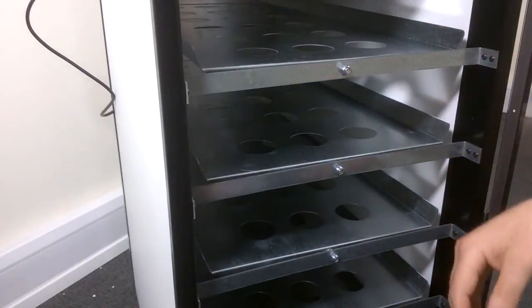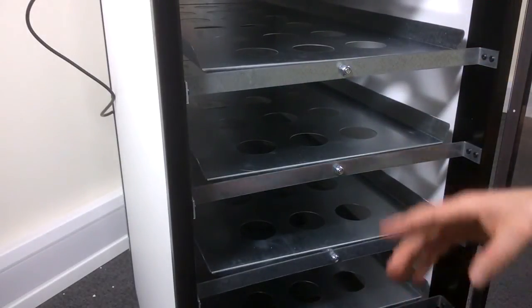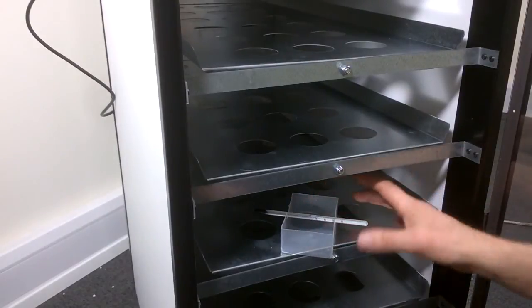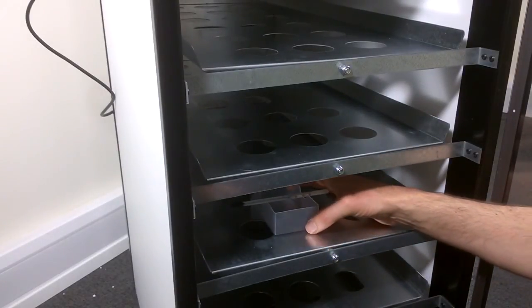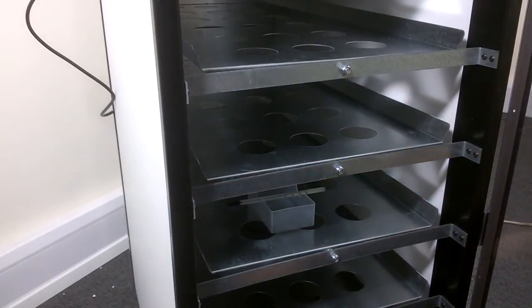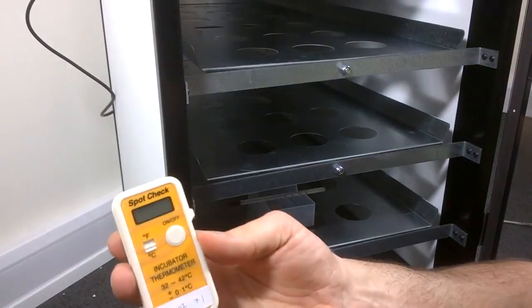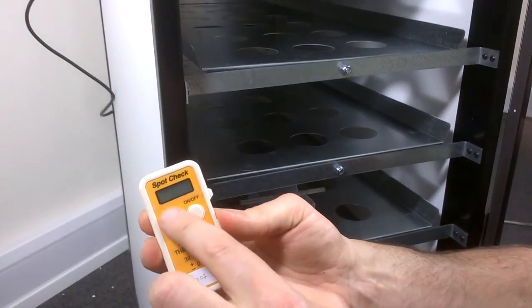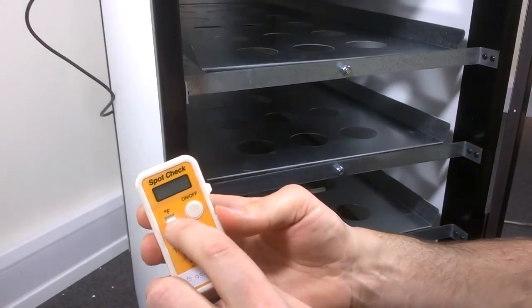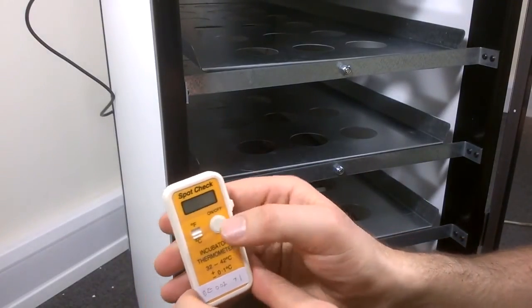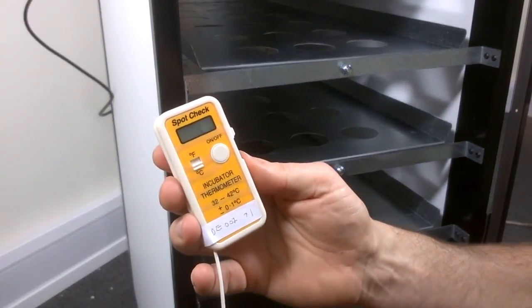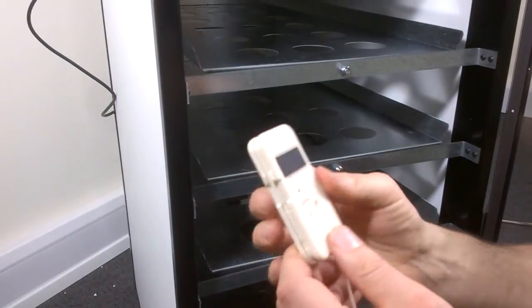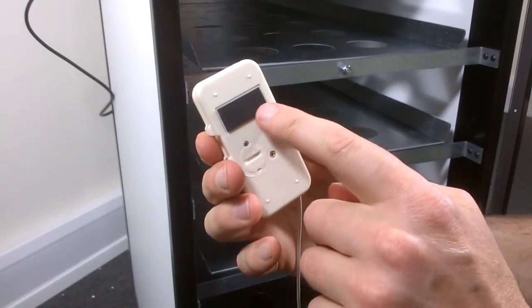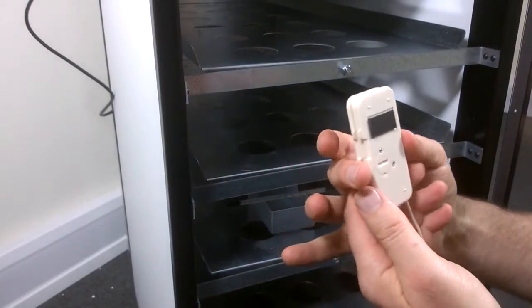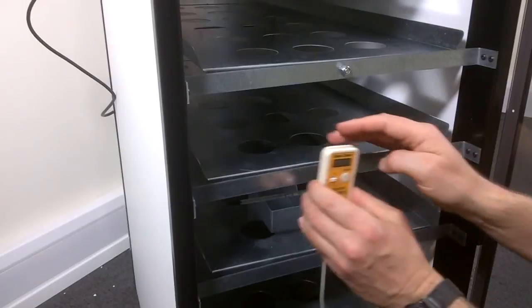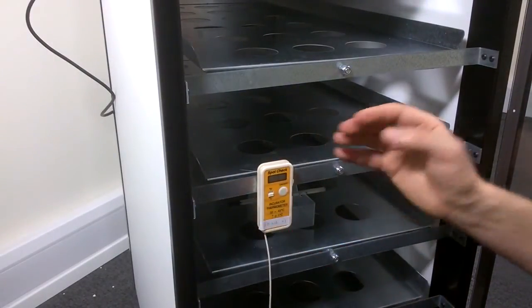I've got the water reservoir fitted, my shelves are flat. I'm going to put my thermometer on the third shelf down in a position where I can still read that temperature. If I'm using the spot check thermometer, that spot check thermometer has a little on and off button. It's also got a little button that tells us whether it's in Fahrenheit or centigrade. I'm keeping it in centigrade. I'll press that into an on so that the little spot check thermometer comes on. The guys in the factory, they place a little piece of magnetic strip on the back, and the beauty of that is that they can clip it magnetically to the front of the machine and close the door.